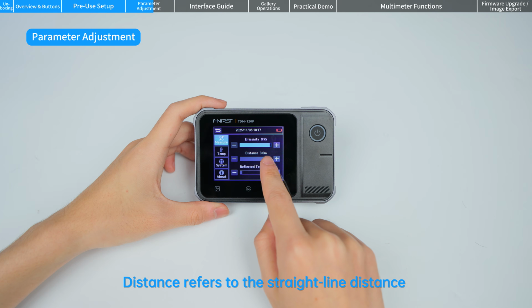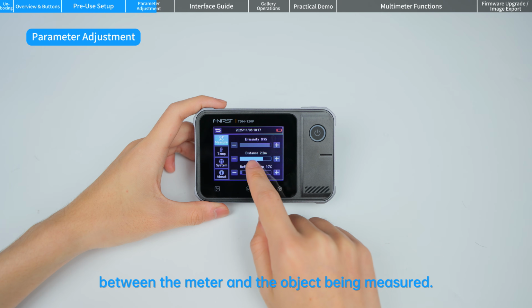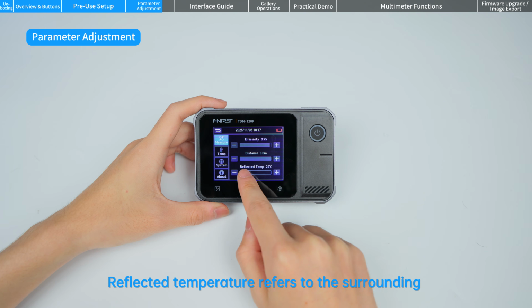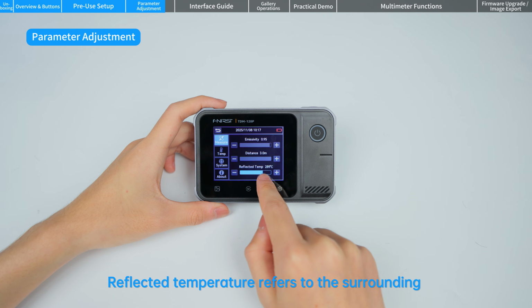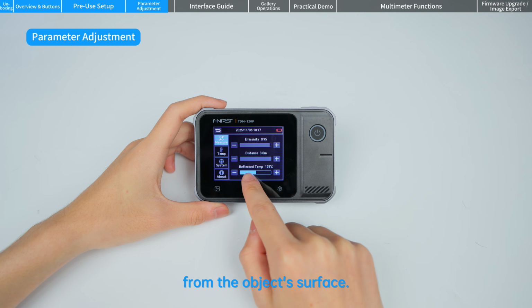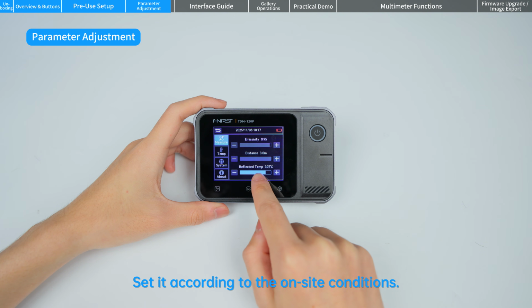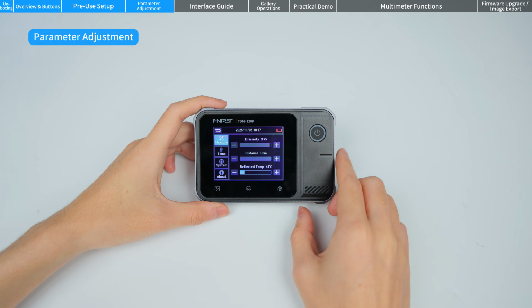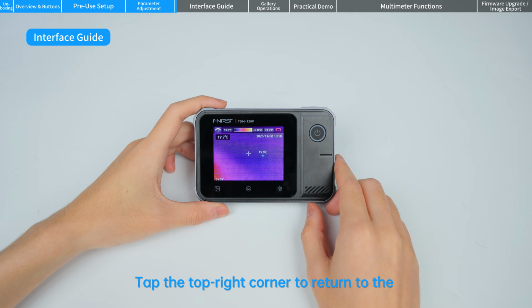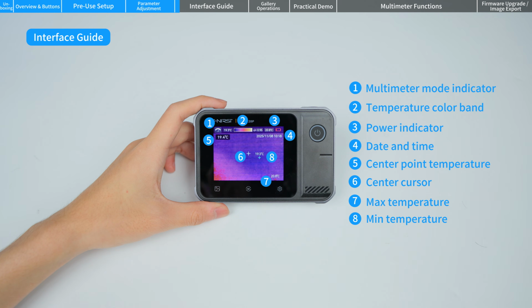Distance refers to the straight line distance between the meter and the object being measured. Adjust it based on the test conditions. Reflected temperature refers to the surrounding ambient temperature reflected from the object's surface. Set it according to the on-site conditions. Tap the top right corner to return to the thermal imaging screen.